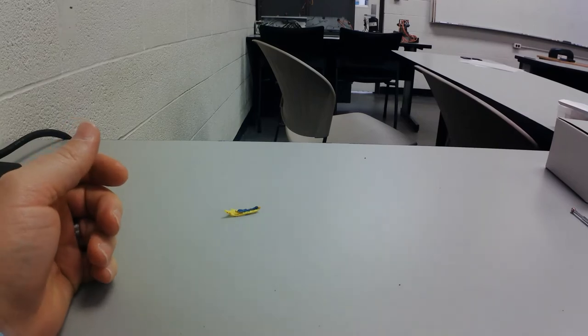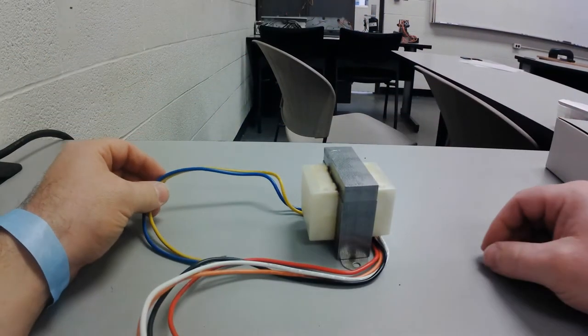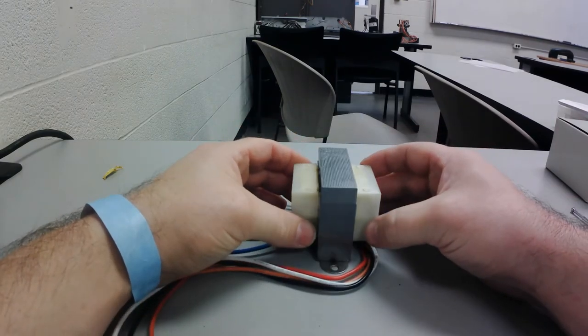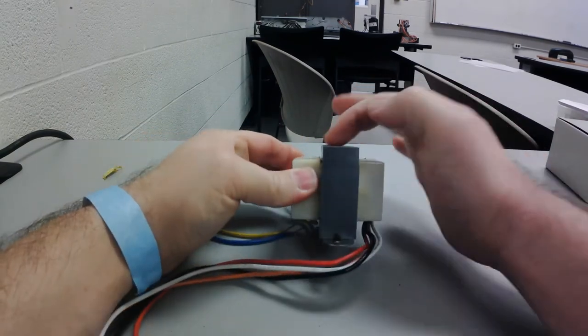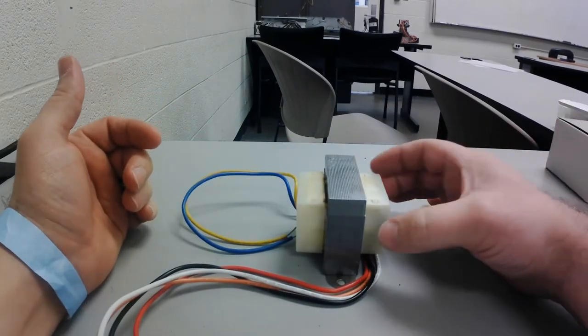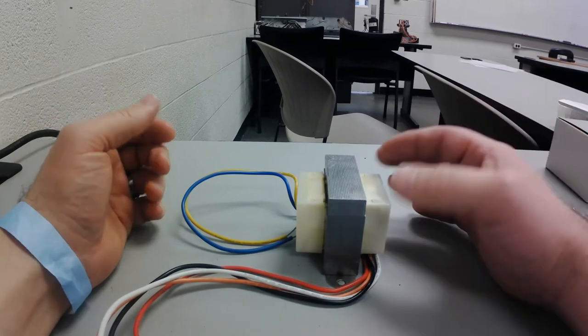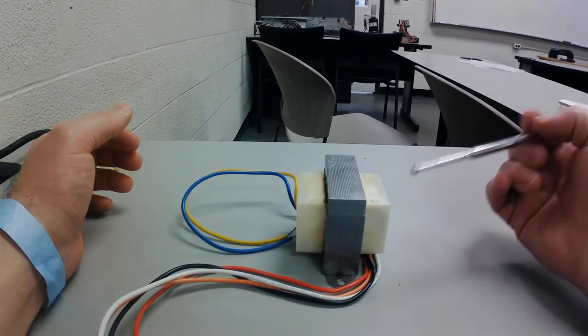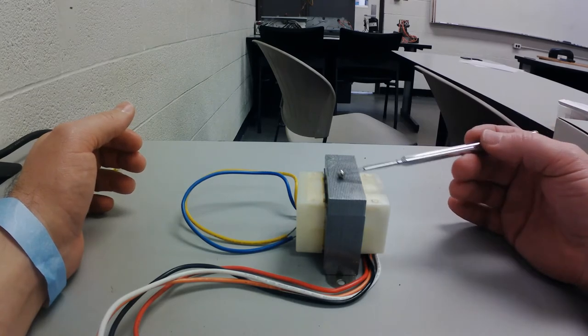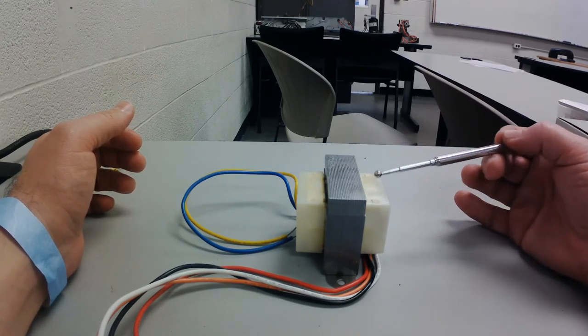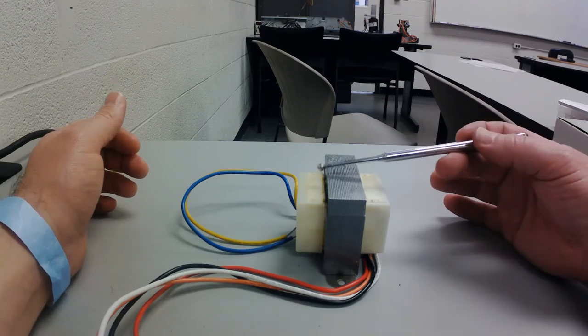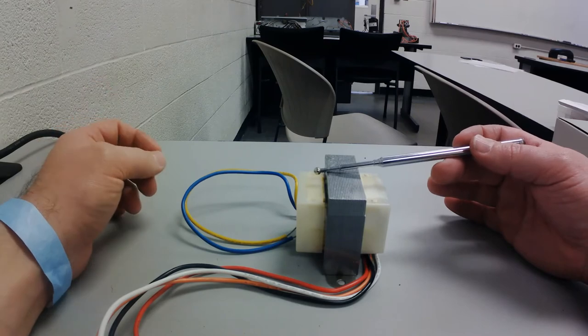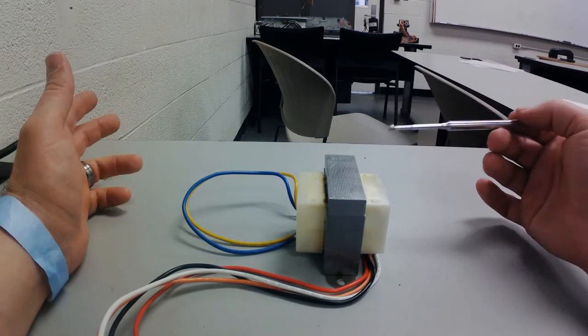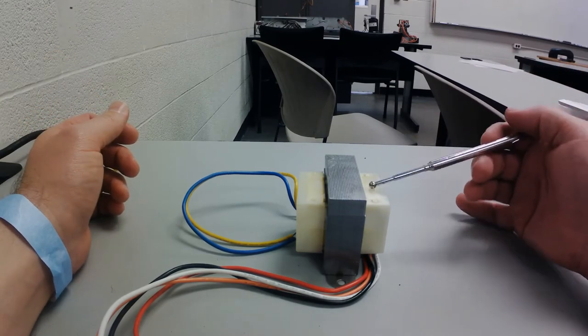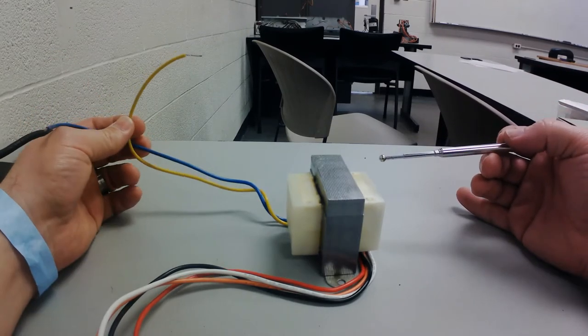So what I'm going to do is show you a brand new one out of the box. Okay, it looks the same underneath as most transformers do. There are two windings, and we've got the iron core in the middle. And of course, as the primary gets the voltage of the system, whatever that may be, it is going to cause an electrical field. Basically, it's going to be a magnet here, and the electrical field around it is going to induce a voltage into the secondary side. So the 24 volts that we have, it doesn't plug into a wall. It gets its power based off of the magnetic field created by the primary side. So 24 volts is here.